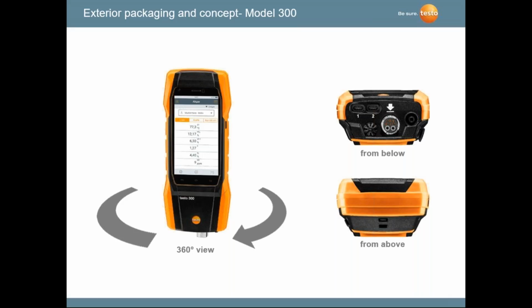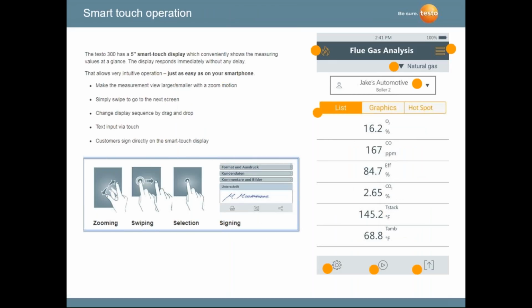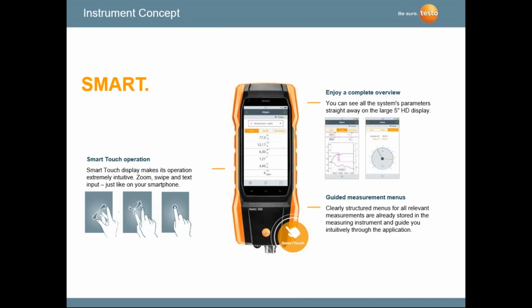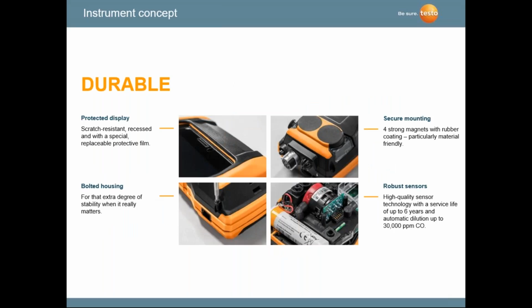From the bottom, this is where your probe and hose connect. There's other locations where additional probes can go if you're doing primary air temperature, things of that nature. Very easy to use, very large graphic display, giving you the whole list of your measurement and calculated parameters, so you can see everything simultaneously without scrolling through different screens. You get the actual numbers, the oxygen reading, the CO reading, the efficiency reading. You also have graphics, so you can look at a graphic representation of these gases, and by zooming and swiping and selecting things, it's just like operating a cell phone. Very simple to use, very smart, very quick. Like I said, graphic representation, guided menus, so you don't really get lost in the navigation of the operation of the instrument. As I said, it's very durable.